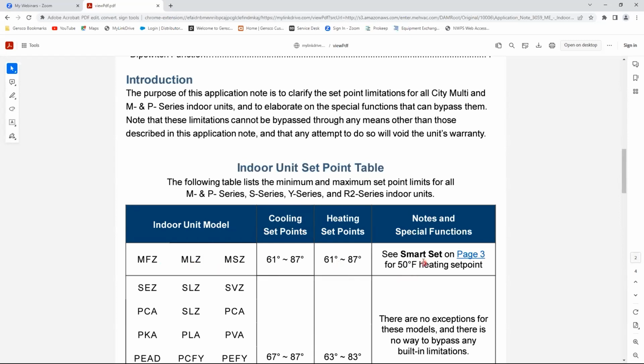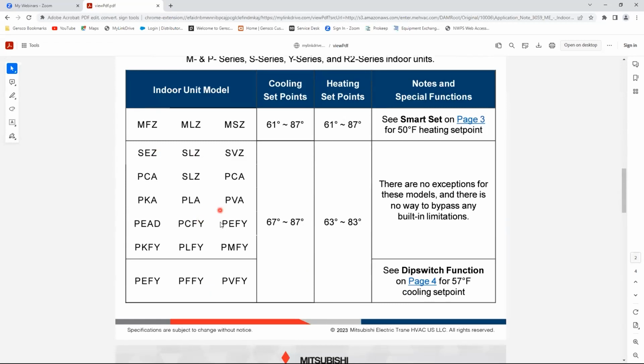And I talked about a 50-degree heating set point. Well, if your indoor unit has smart set, you can get down to that, and page 3 explains how to do that. On all of the other units, SEZs through PMFYs, our cooling set point is 67 to 87, and our heating set point is 63 to 83. Now, if you have one of these 3 city multi-units, city multi-unit units end in FY. City multi-units have the metering device in the indoor unit, unlike the P series and M series. So if you have one of these 3 units, you can get to a cooling set point of 57 by setting dip switches, and page 4 will walk you through that.